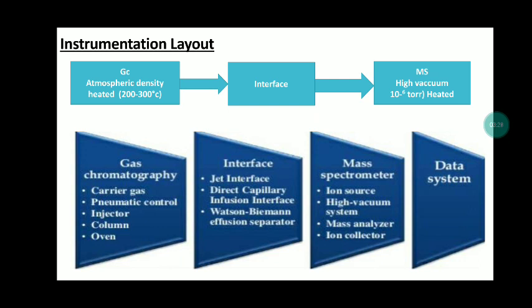Instrumentation of GCMS. This is a layout of the GCMS. The GC and MS systems are both heated at 200 to 300 degrees Celsius and both deal with compounds in the vapor state. The interface is a connection between GC and MS and plays an important role in GCMS. The pressure incompatibility problem between GC and MS is solved by inserting an interface, because MS operates under vacuum at 10 to the power of minus 6 torr, whereas GC operates at high pressure.